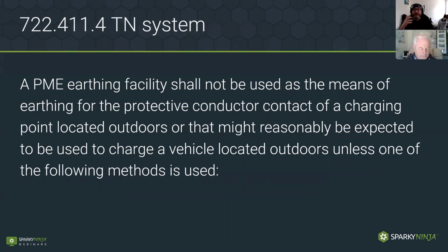It then starts by introducing protection against electric shock by again saying that a PME earthing facility is not to be used as the means of earthing for the protective conductor contact of the charging point located outdoors. There are a couple of exceptions to this. So it starts off by saying no. If you're on a TT or a TN-S, then that's fine. This is TN systems PME. Let's get that out there first. So we're looking at TN-C-S situations.